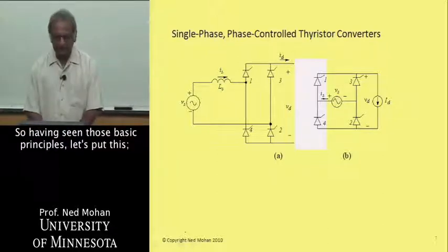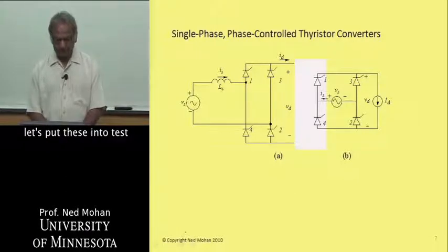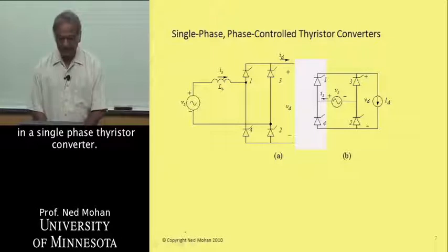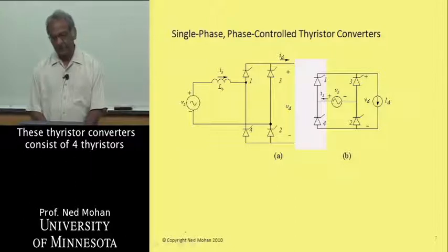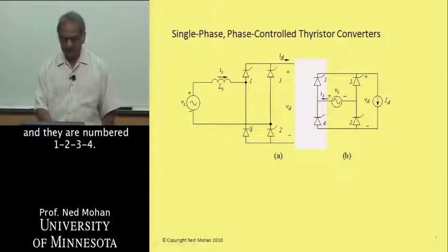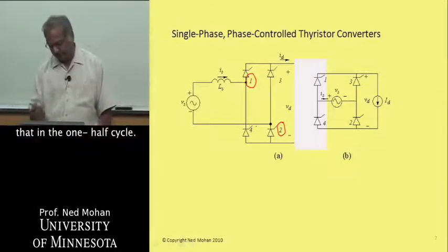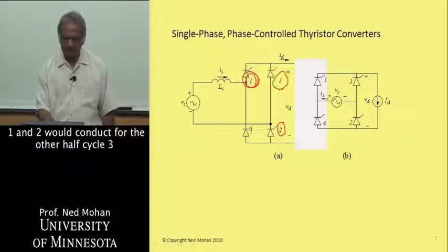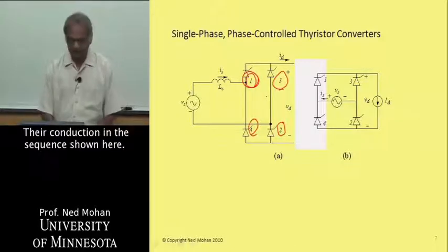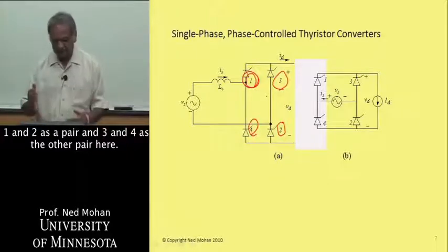Having seen those basic principles, let's put them to test in a single-phase thyristor converter. These thyristor converters consist of four thyristors numbered one, two, three, four. For one half cycle, one and two would conduct, and for the other half cycle, three and four would conduct. They will conduct in the sequence shown here — one and two as a pair, and three and four as the other pair.